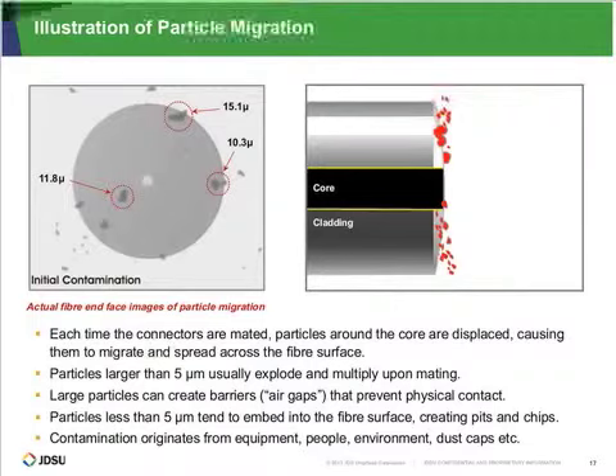And what's been found is that the size of the dirt particle has a very big effect on what happens. So particles that are 5 microns or less tend to be pushed into the glass and tend to stay there. They embed themselves in the surface. Particles that are bigger than 5 microns are too big to be pushed into the glass. They tend to just break up and spread themselves over the end face.